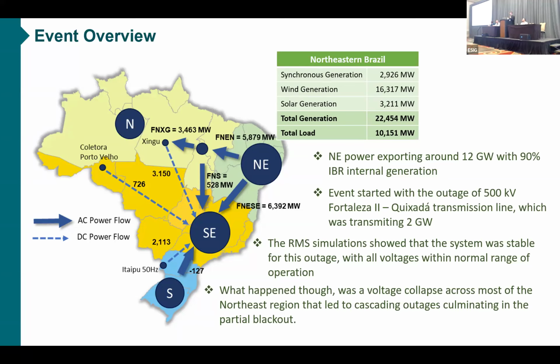The system's plan and its operator expected that, as a single outage, it shouldn't cause any damage. The RMS simulation showed the system was stable for this outage, with all voltages within normal operating range. But what happened was a voltage collapse across most of the Northeast region, leading to cascading outages and a partial blackout affecting the North and Northeast regions. So what explains the difference between the simulation showing controlled voltages and the reality of a voltage collapse?